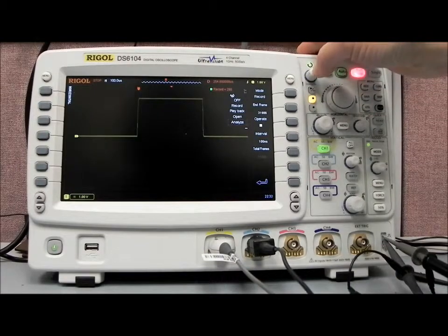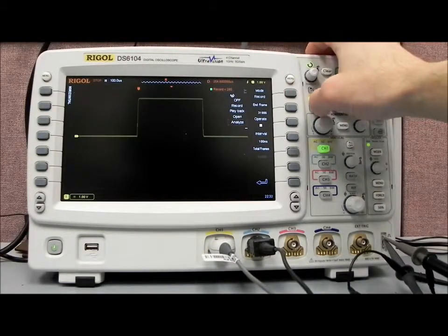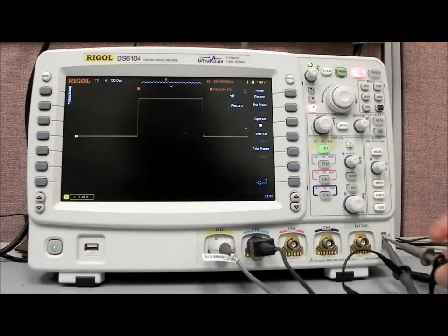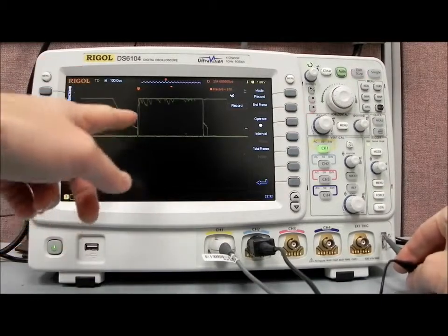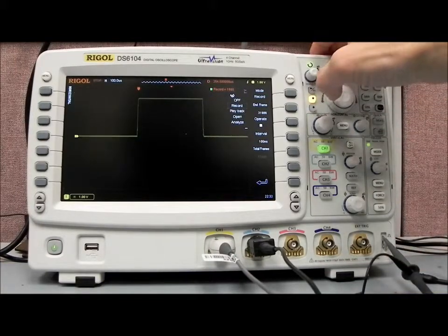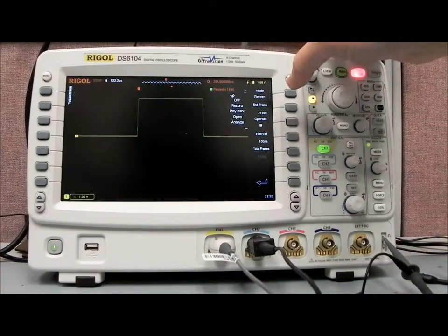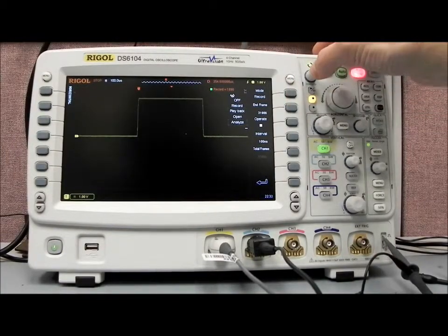And now what we can also do is actually analyze that data. Actually, I'm going to record some failures, so we're going to go back to recording. And now I'm going to select channel 1, and I'm going to just pull it off the probe compensation point, and you can see now we're getting some different values here. And then I'll place it back on, and now I'll stop. So we've collected 1,890 frames. Now let's go to Analyze.